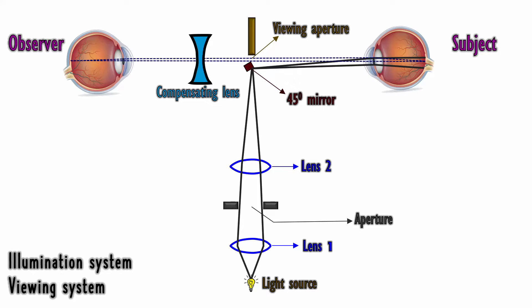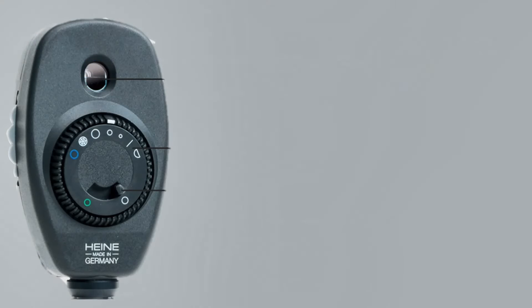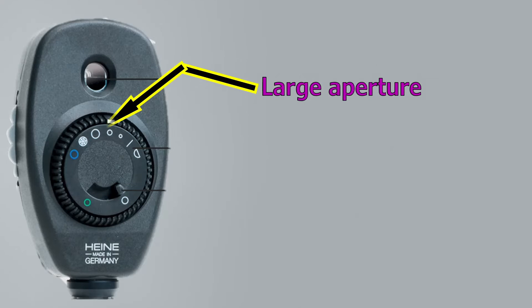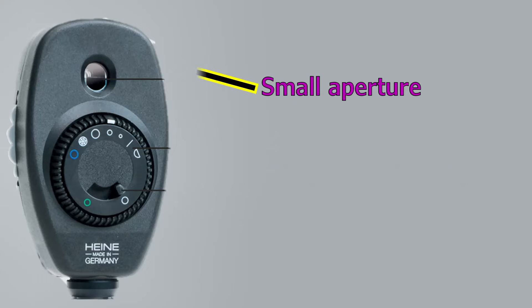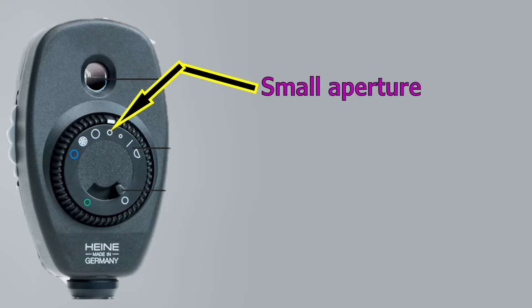The type of aperture can be controlled by means of a thumb wheel. The various apertures available are: a large aperture for standard fundus examination under dilatation, and a small aperture for viewing the fundus through an undilated pupil.